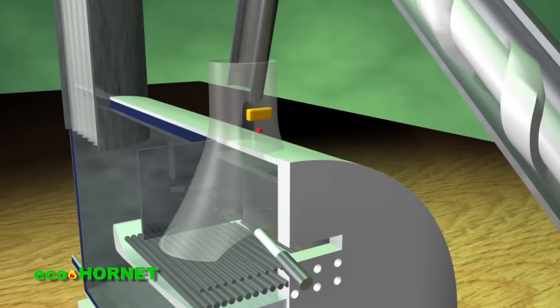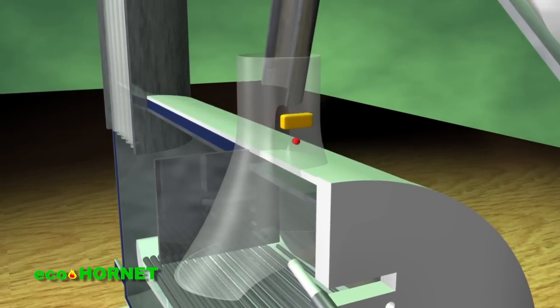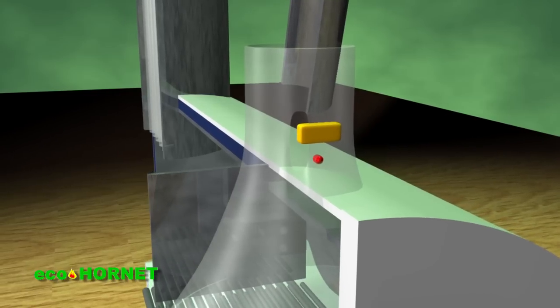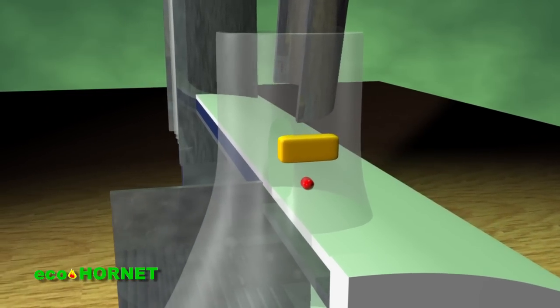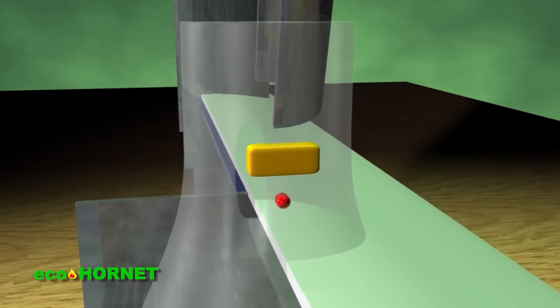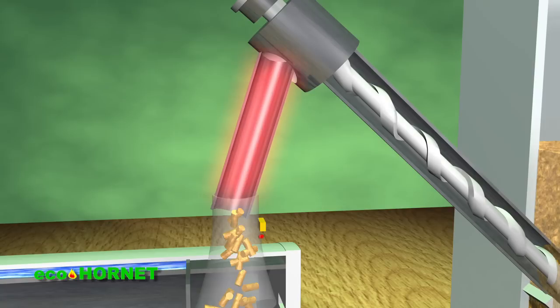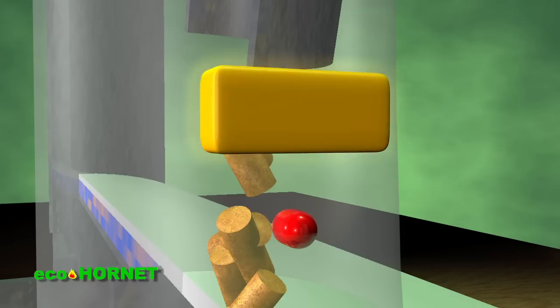The pellet level in the combustion chamber is measured by means of a level sensor that maintains a constant level of fuel above the grate and that keeps a pellet-free area at the level of the supply tube, thus preventing the flame from spreading to the worm gear and to the bunker. The level sensor is protected both by placing it on a flame-retardant wall made of glass textilite and by placing a temperature sensor that interrupts the feeding process when a temperature of 60 degrees Celsius has been reached on the metal surface of the pipe.